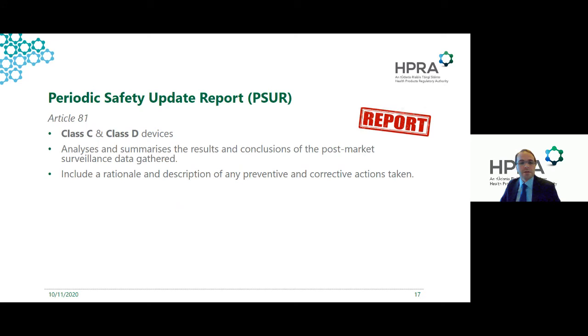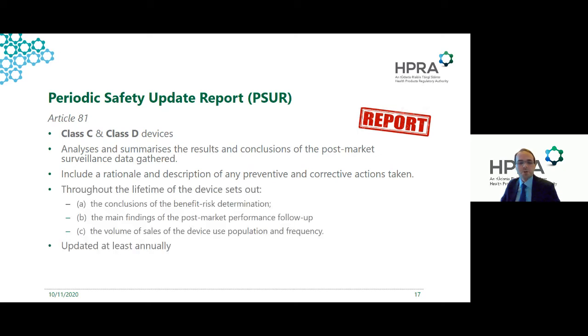As you identify the need to update it, you make the updates. For Class C and Class D devices, the report is called a periodic safety update report. Again, it analyzes and summarizes the results and conclusions of post-market surveillance data, looking at rationales and descriptions of any actions taken on the market. But it also sets out that throughout the lifetime of the device, you're looking to conclude on the benefit risk determination—does the benefit risk still equate? Is it still a positive benefit risk ratio? You also look at the main findings of the post-market performance follow-up in your PSUR, rationalized generally in terms of the volume of sales, the use of the device in the intended population, and the frequency of use.